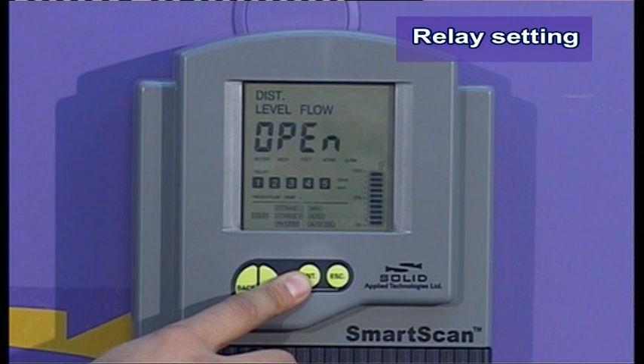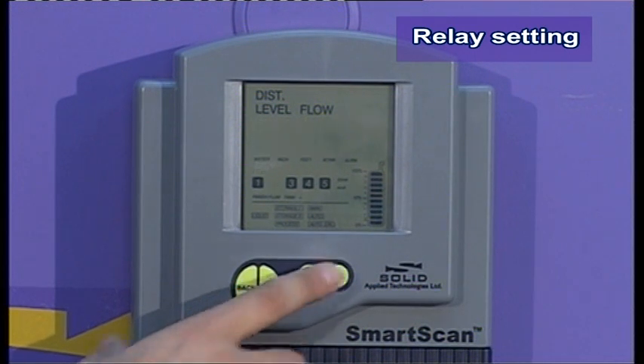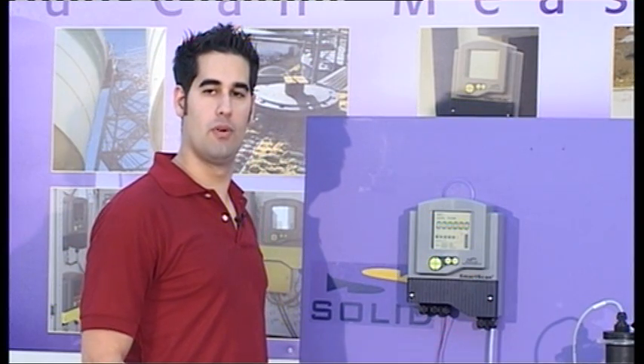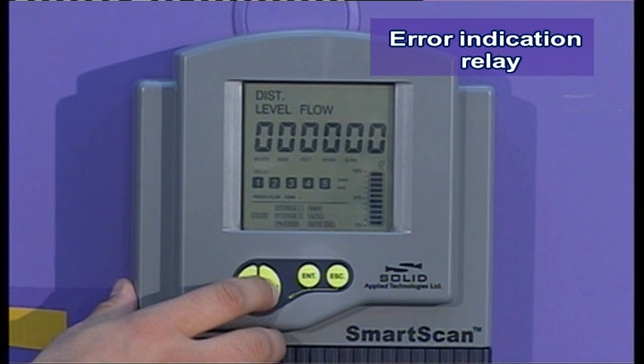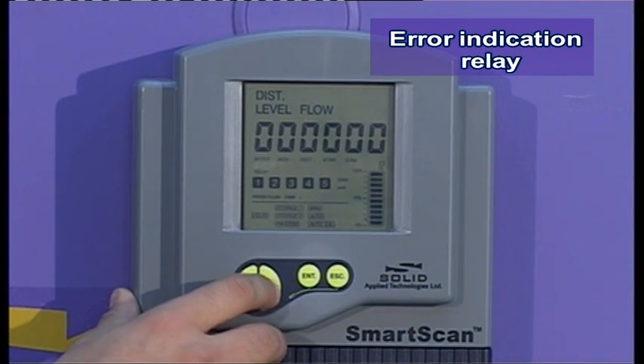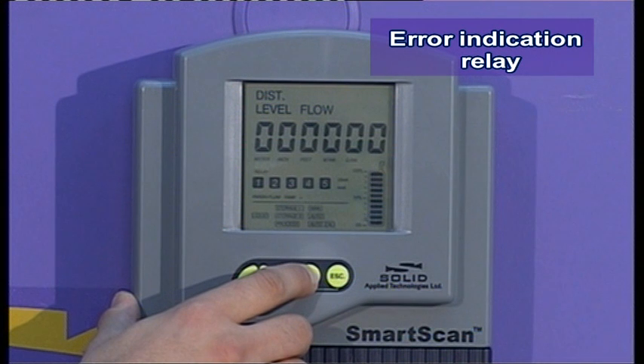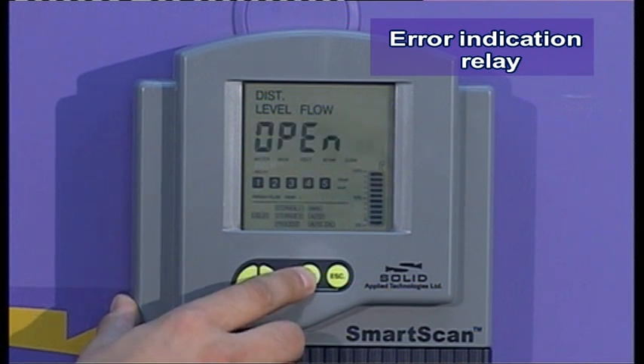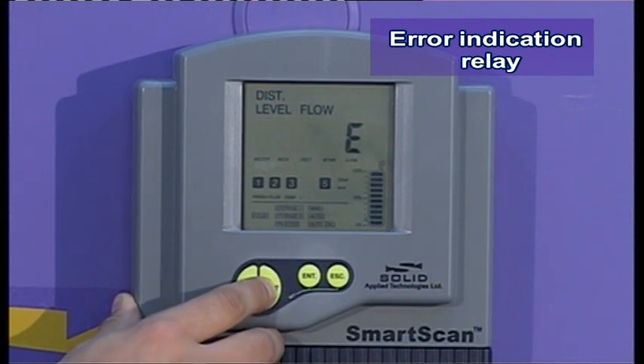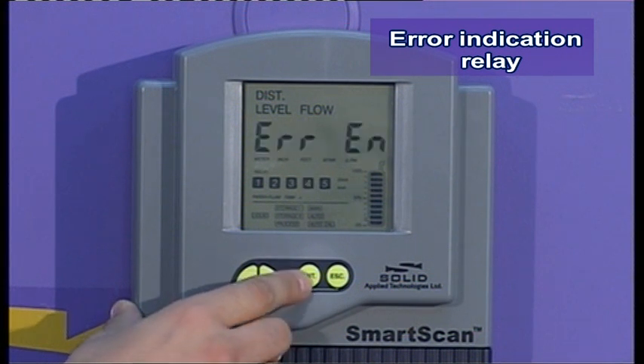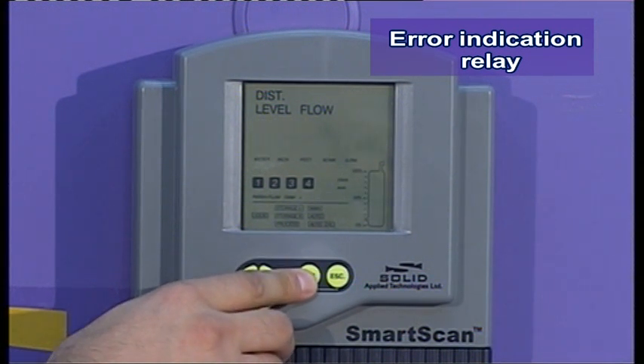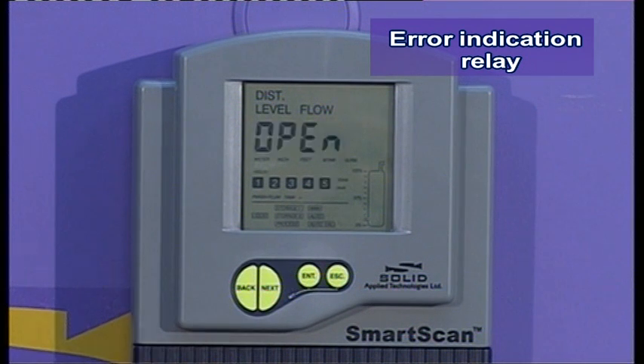With this option, we've made a hysteresis window from 1.5 meter to 1 meter. Relay number 4 behaves as an error indicator, which means if I go through relay number 4 and choose error enable function, every time SmartScan indicates an error, which means empty error or full error, the relay will energize.